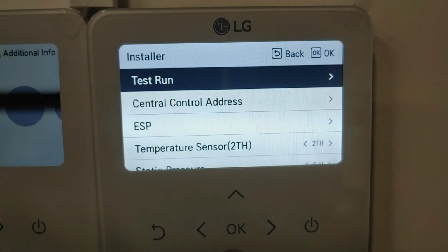Depending on the ductwork, depending on the job application, we can set values for low and medium speed lower. It should be lower than selected setting for specifically this ductwork, and in the range of the setting value for our indoor unit. In our example, 60 is the minimum setting, so let's say we set 60 on the low speed and medium something in between, let's say 75. Again, double check with engineer and make sure that user knows that airflow will be lower with low and medium speed of fan.